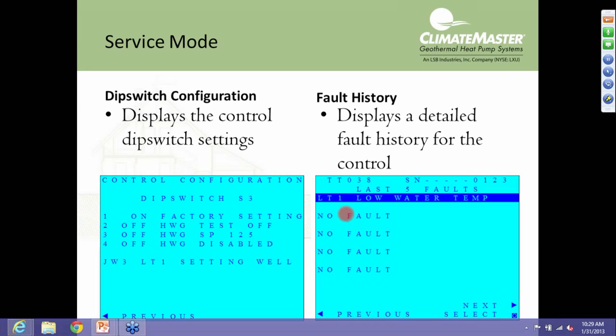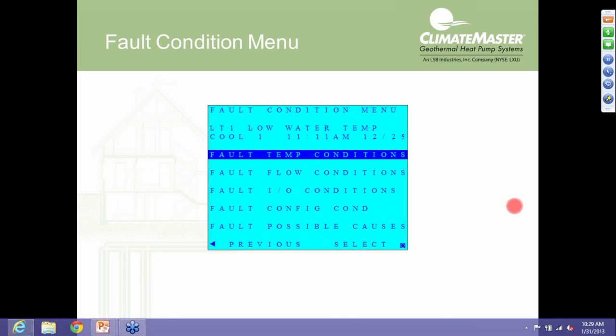Next, we have our fault history. Again, we can display up to 5 faults. You see one fault here that's highlighted, LT1 low water temp fault. So we can select it, and once we select it, we can look at conditions at the time of that fault. The first thing would be the fault temp conditions, fault flow conditions, I/O conditions, configuration conditions, and then possible causes.